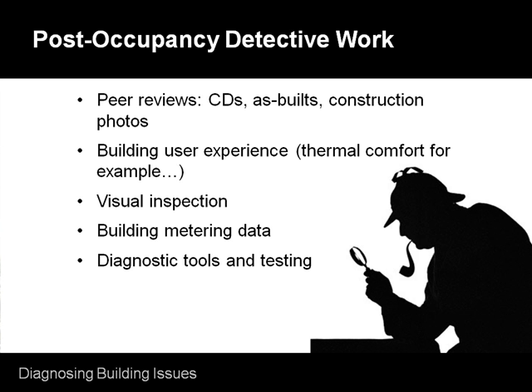So, things that you can do to performance validate after the fact. Strong recommendations, whether required by LEED or required by what we've heard up front. Simple things like air tightness tests, about 25 to 30 cents a square foot of building enclosure. So that's not an enormous amount of money when you're talking about a building enclosure that could cost hundreds of thousands of dollars with systems and claddings in front. Maybe that $25,000 spent up front is money well invested in terms of finding the things you would actually have to do after the fact.